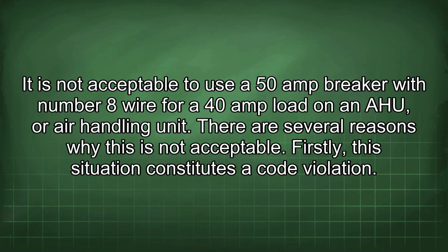It is not acceptable to use a 50 amp breaker with number 8 wire for a 40 amp load on an AHU, or air handling unit. There are several reasons why this is not acceptable. Firstly, this situation constitutes a code violation.